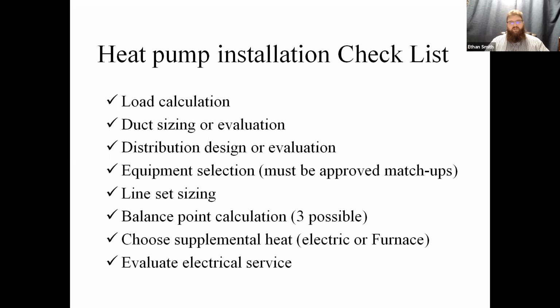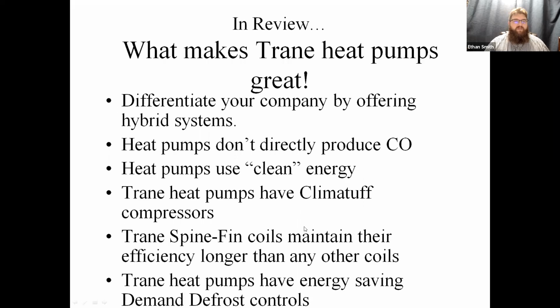So make sure you know how your homeowner and what they're expecting out of their heat pump, and make sure that you're delivering that. Make sure your supplemental heat is going to be adequate to supply heat to the house, whether you're planning on shutting the heat pump down completely and satisfying all of the heat requirements with the supplemental heat at a certain temperature, or whether you're going to run them concurrently. Make sure that you've got the electrical service both indoors and outdoors in order to satisfy your electrical needs for the heat pump. So just kind of a little checklist, guys. Make sure that you've got everything.